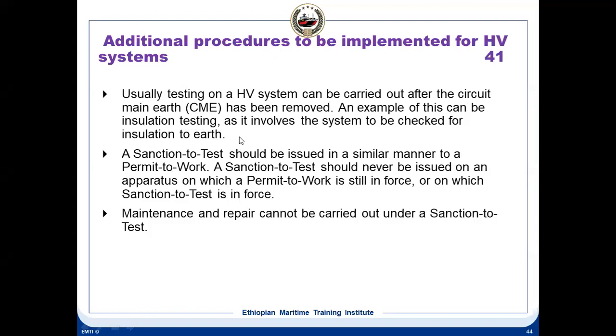The grounding is done at the initial stage, and once you know that there are no residual charges, you check with the probe that there are no residual charges, you can remove the ground and you can work. So the grounding can be removed. It's not that the ground is always connected, because for a Megger test and all, you have to remove the grounding. So grounding can be removed.